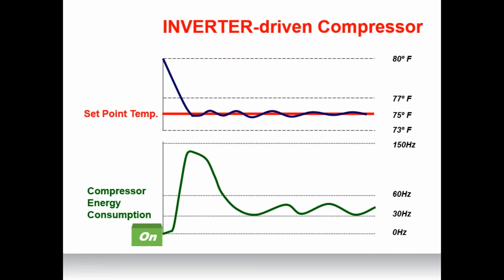An inverter-driven system is completely different. Upon starting, inverter compressors ramp up speeds beyond traditional systems, in order to rapidly bring the temperature down to the desired set point. Once the set point temperature is reached, the fan rotation speed is maintained at low levels. This maintains a consistent energy usage as well as a consistent temperature, to avoid those drifts and energy consumption spikes.